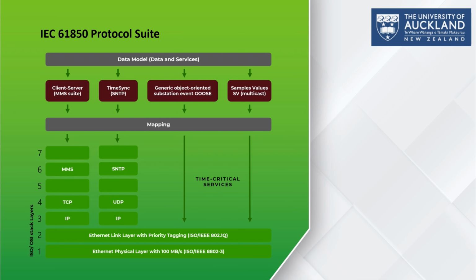speed and priority are essential for GOOSE and SV, these messages bypass TCP, UDP, and IP and are carried directly over the Ethernet link layer with priority tagging. This tagging ensures that protection-related messages are given priority over normal traffic. At the bottom, all communication ultimately relies on the Ethernet physical layer, that is IEEE 802.3, typically operating at 100 Mbps speed, right?